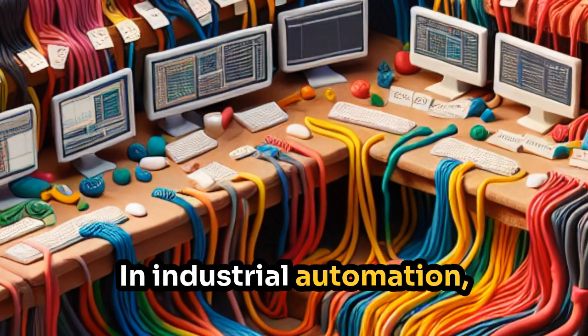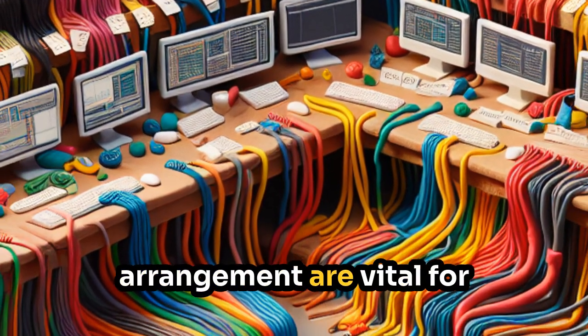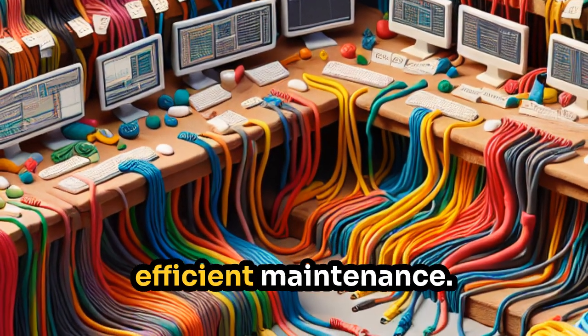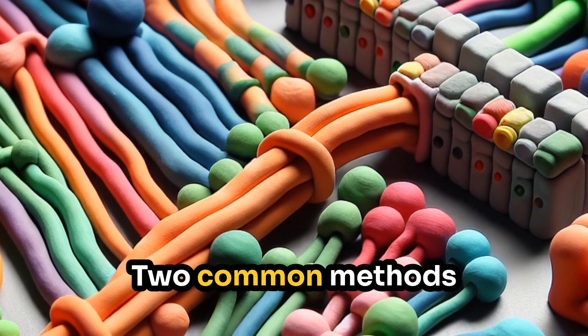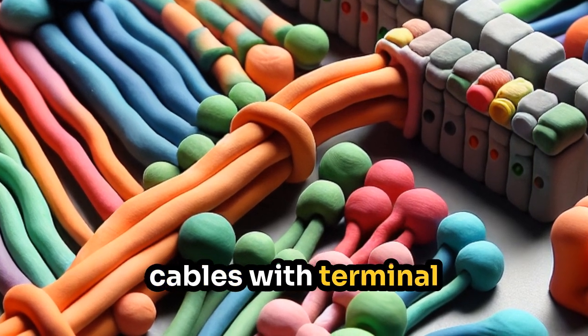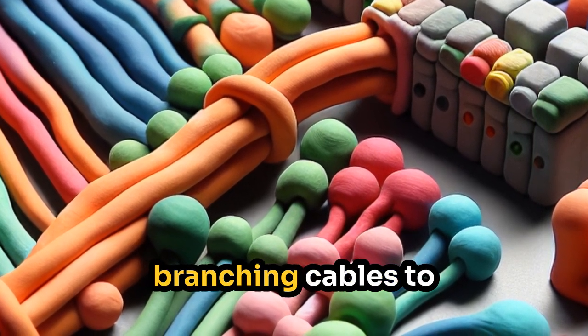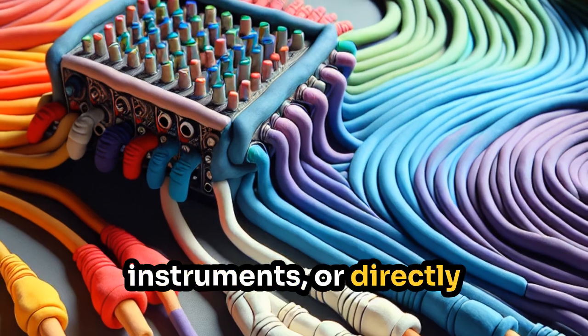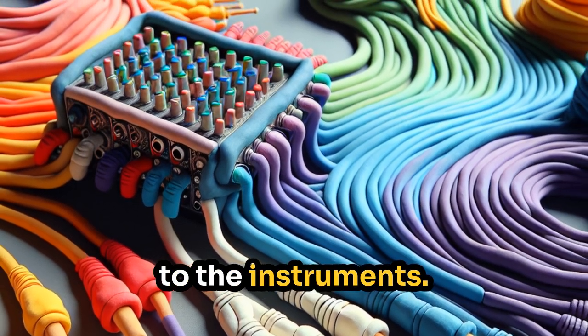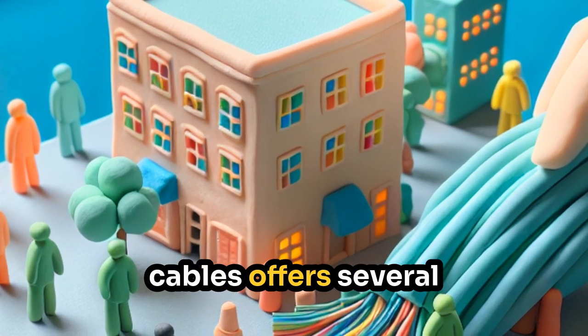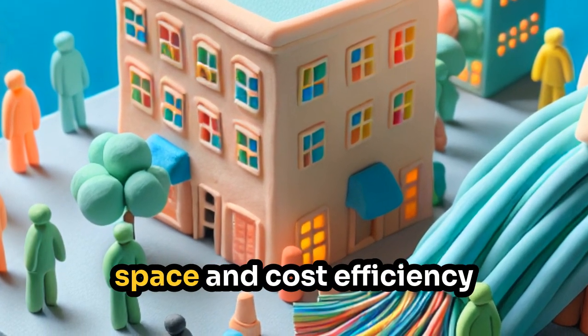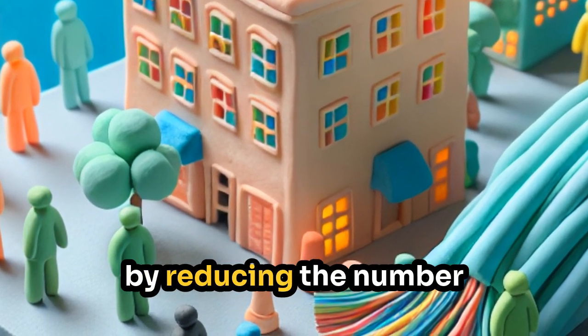In industrial automation, cable selection and arrangement are vital for ensuring stability and efficient maintenance. Two common methods are using multi-core cables with terminal junction boxes and branching cables to instruments, or directly connecting cables to the instruments.